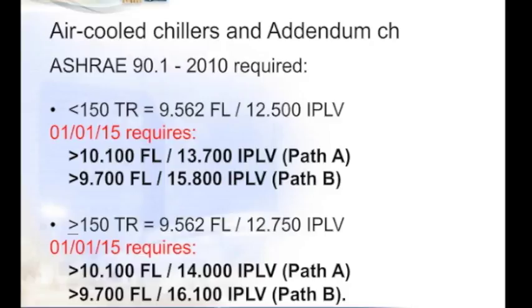Now I'd like to share a few numbers about the efficiency requirements for air-cooled chillers. The purpose of the information on this slide is to clearly indicate what the values used to be and what the values will be now after the January 1st implementation of these efficiency increases. As you can see, the efficiency for chillers less than 150 tons is going from 9.56 full load efficiency and 12.5 IPLV to 10.1 full load and 13.7 IPLV, if following compliance path A. The requirements if path B is followed are 9.7 full load and 15.8 IPLV.